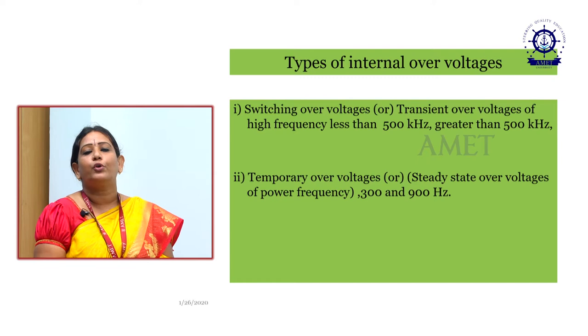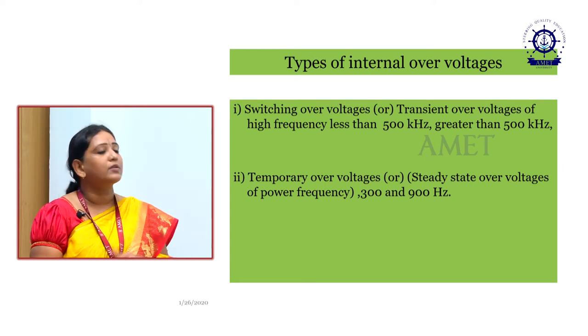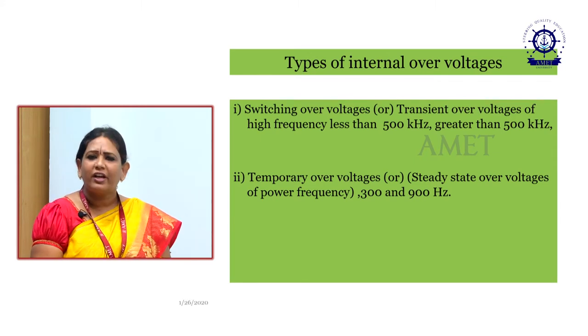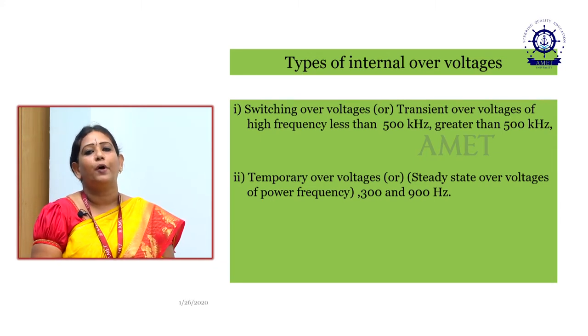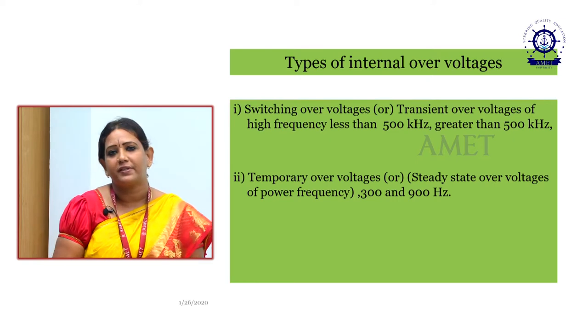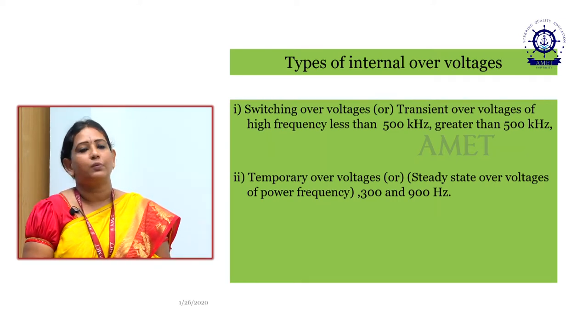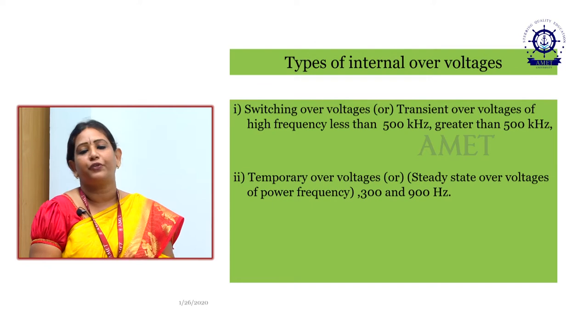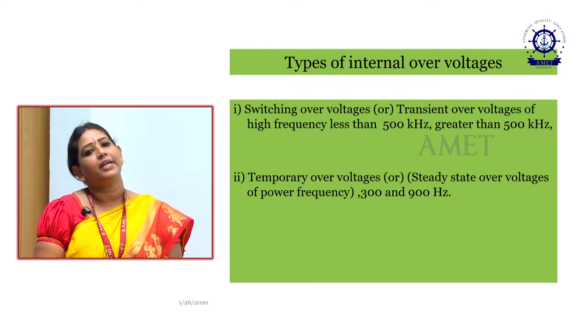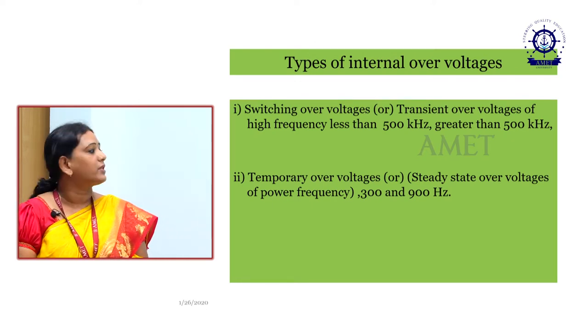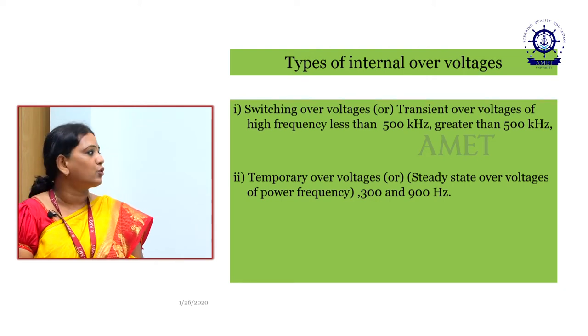And the next one is the temporary overvoltage. From the name itself, it's very clear. It is a steady state, so it is not varying or transient like the previous case, but a steady state overvoltage of only power frequency. What is called power frequency? Power frequency lies in the range of 50 to 60 hertz, as in utility services and domestic loads, which work on these frequencies. And when you go for higher types of loads, the frequency lies in the range of 300 to 900 hertz.